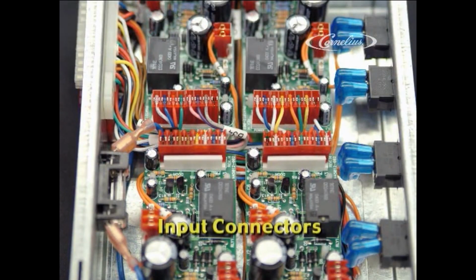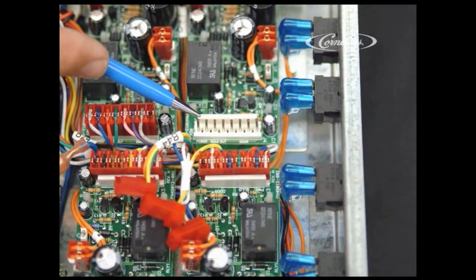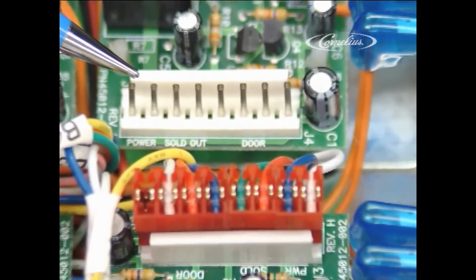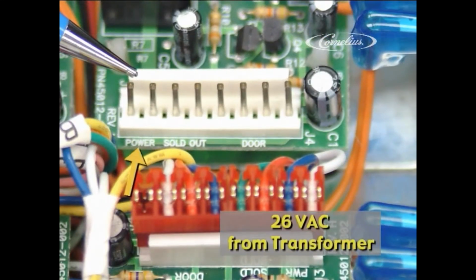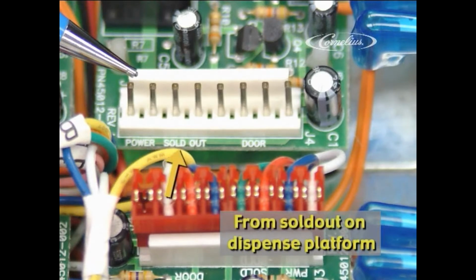This is the long row of connectors mounted at the bottom of the VRB board. Each connector position is labeled. Starting from the left, there is a 2-pin connector marked Power. This is the 26 volts AC coming in from the transformer. Next is a 2-pin marked Sold Out. This is the connection for the sold out system input from the corresponding bottle adapter on the dispense platform. We will review this operation later.